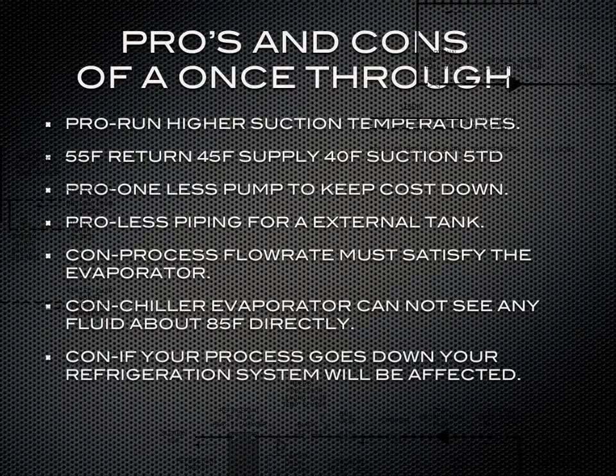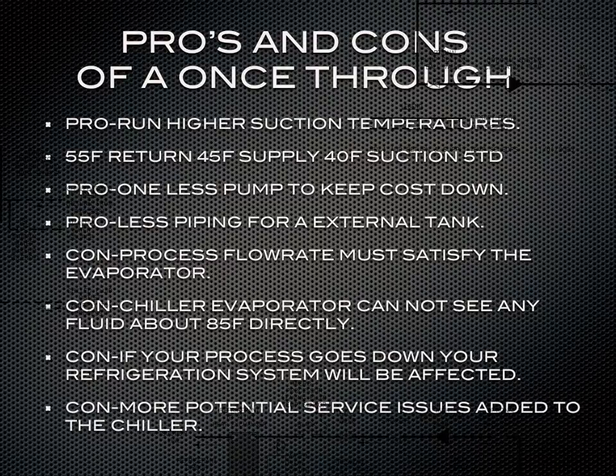Another con is that if your process goes down, your refrigeration system will be affected. Everything's so intertwined into that one loop, and there's so many different variables, and there's more potential service issues added to the chiller because everything's so connected and intertwined. So when you're doing a once-through setup, just keep in mind that there is going to be a little more service issues and potential problems with that.